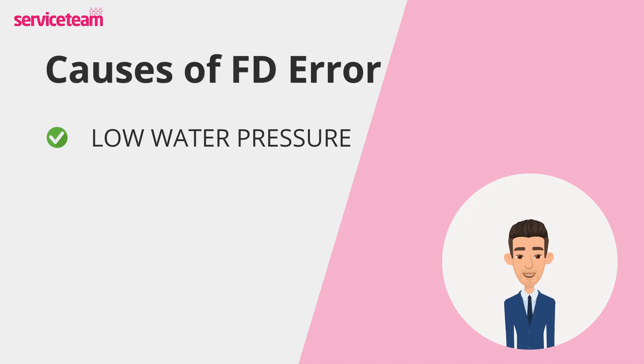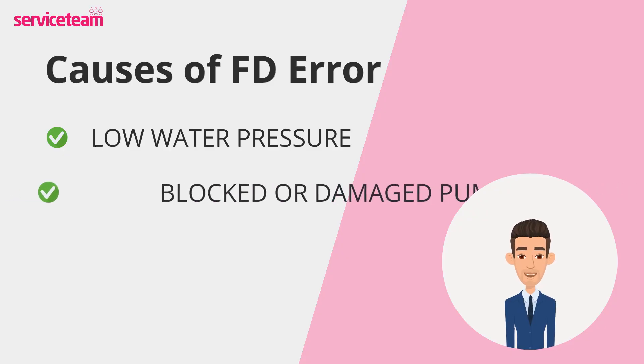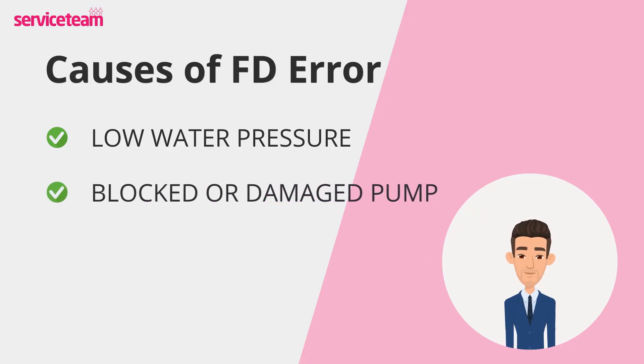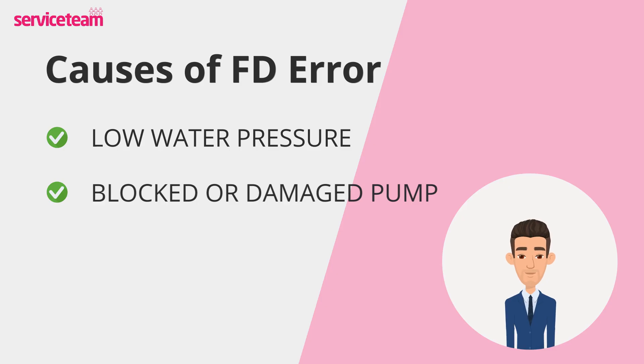If your pressure gauge is looking a little low, that could be your culprit. Next, check the pump. If your boiler is showing the FD error, it could be due to a blocked or damaged pump, which circulates hot water throughout the system.